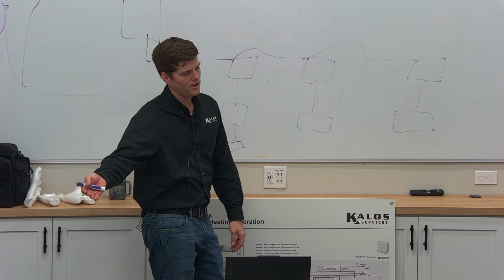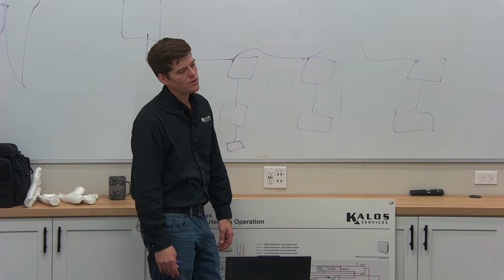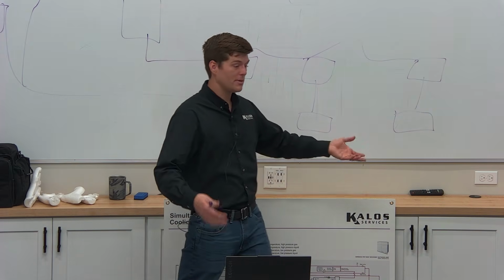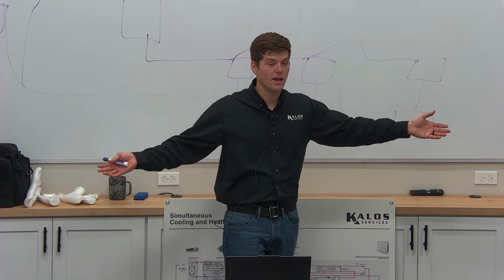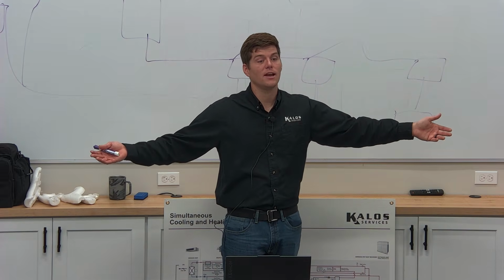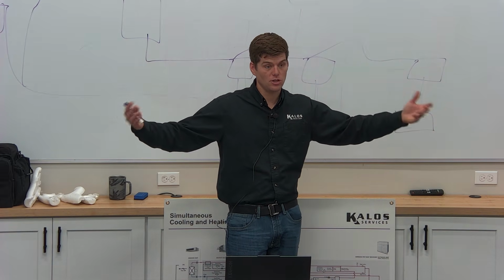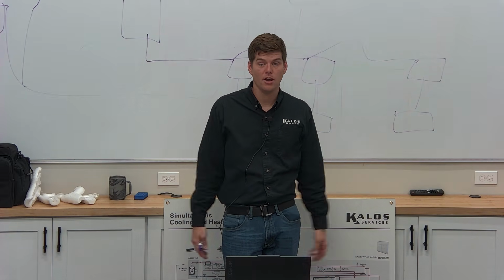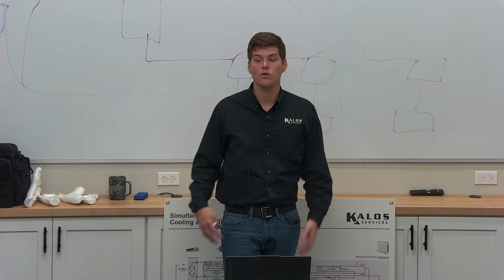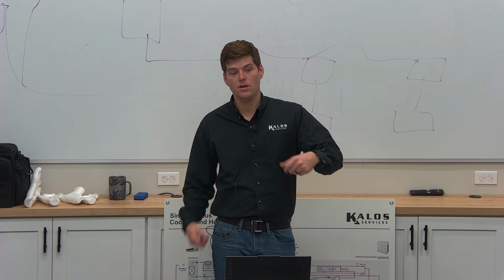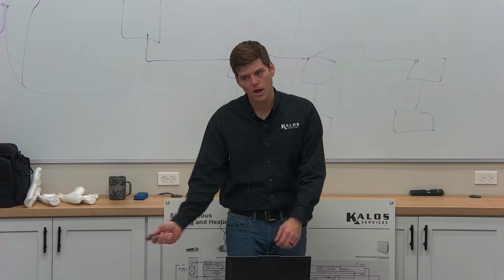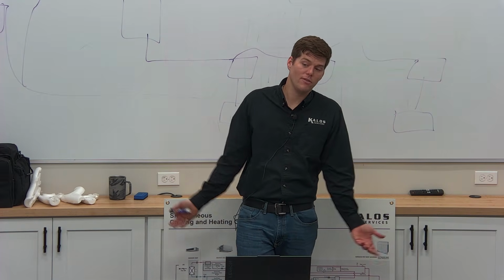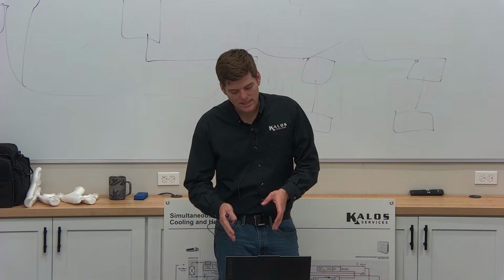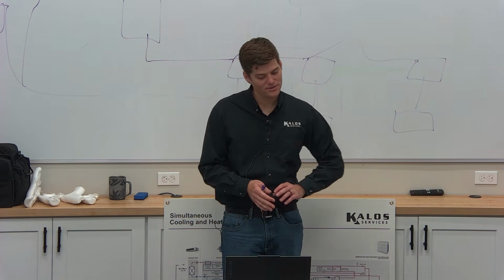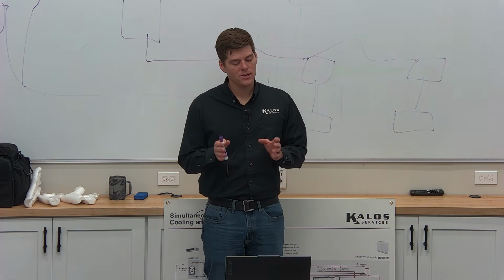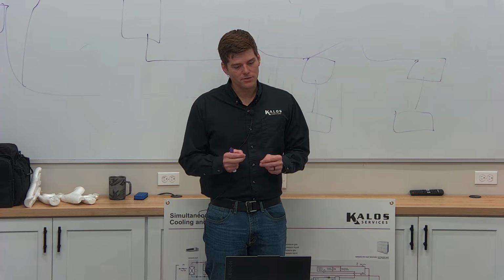If I know I have 15 fan coils and my outdoor unit says I only have 13, it's like, okay, well, who's missing? There are ways to put the system in a specific mode to turn all the indoor fans on to find the ones that are missing from the communication loop. The ones that can talk to it will turn on a fan. I walk inside and find the fans that aren't running. Those are my issues, right? Look at my unit, measure my voltage. I don't have any. Follow the wire. Okay, it got landed on the wrong spot or it never got run in the first place. It has its complexities, I'm not going to lie to you. I'll show you exactly what that looks like. But at a basic fundamental level, it's just two wires.